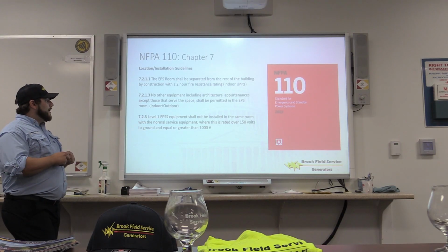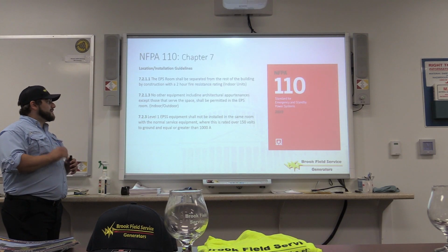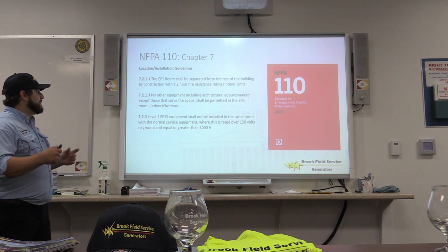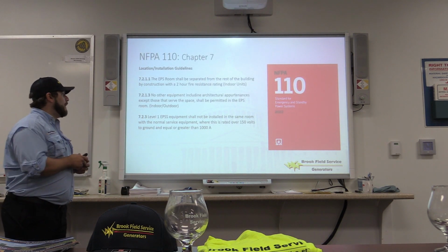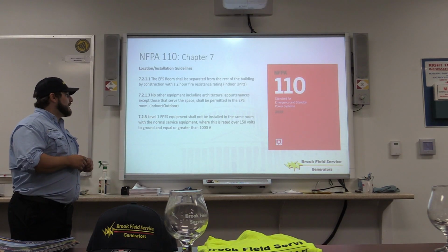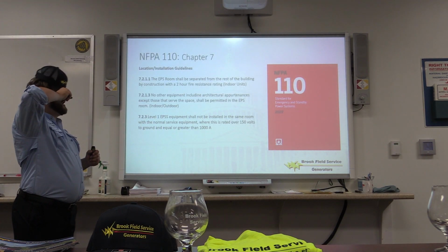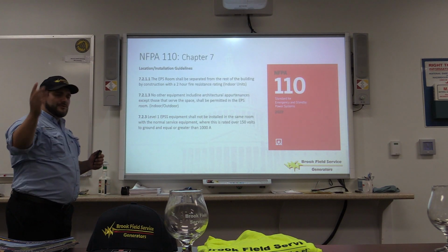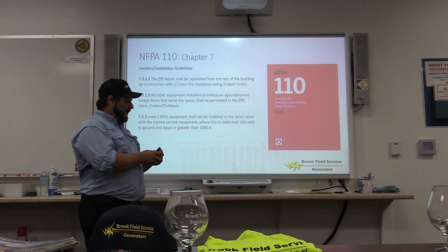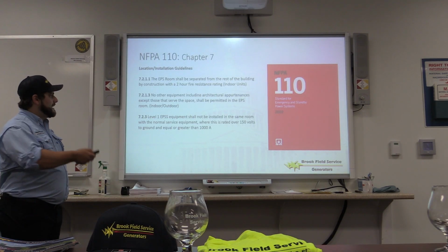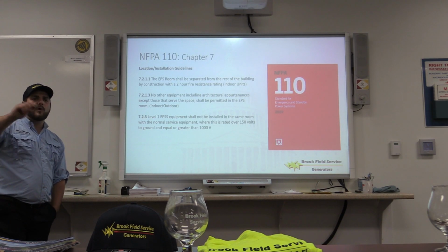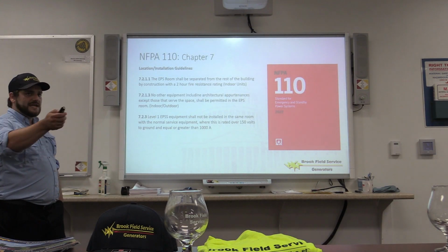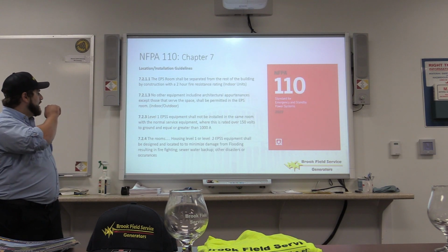Level 1 emergency power supply system equipment should not be installed in the same room with normal service equipment where it is rated at over 150 volts to ground or equal or greater than 1000 amps. You guys don't qualify, I believe, for Level 1, so I'm going to skip over that one. But I know Jim will talk more about that towards the end during his part.